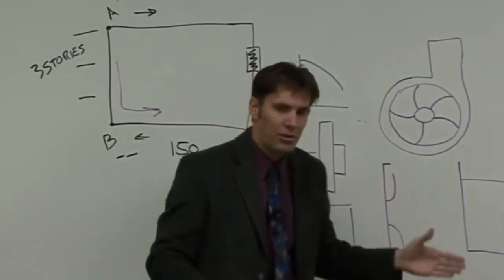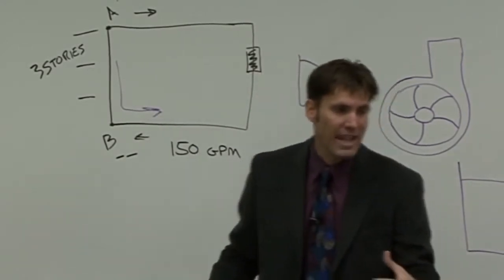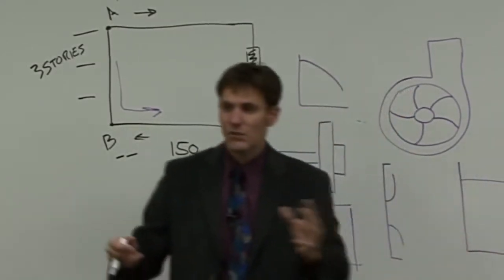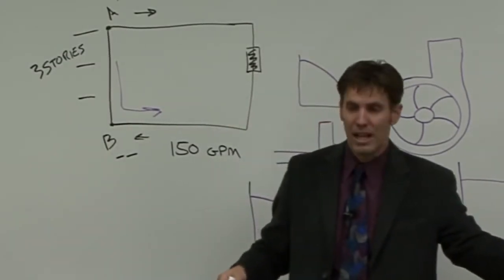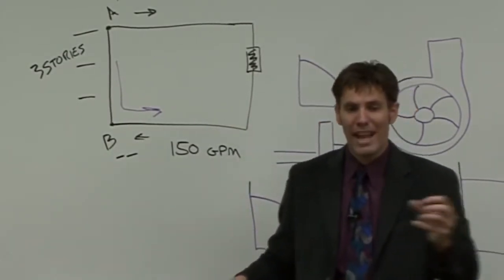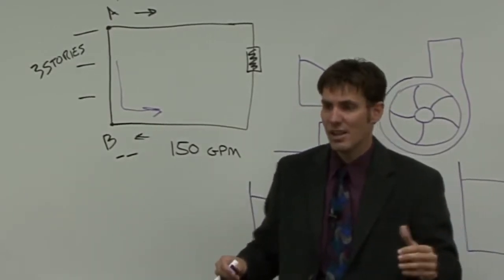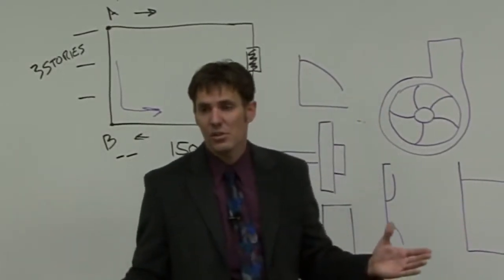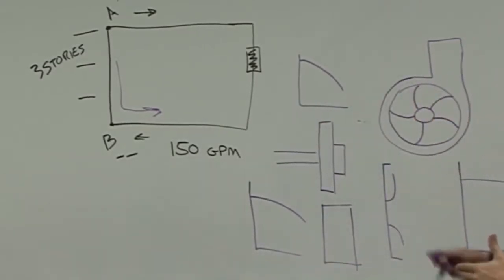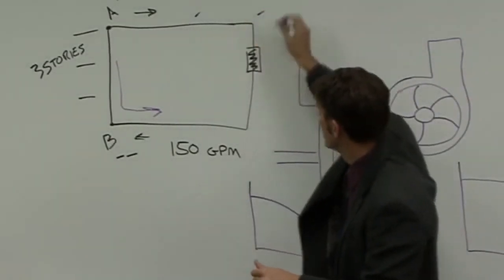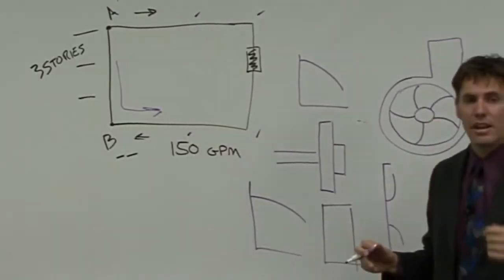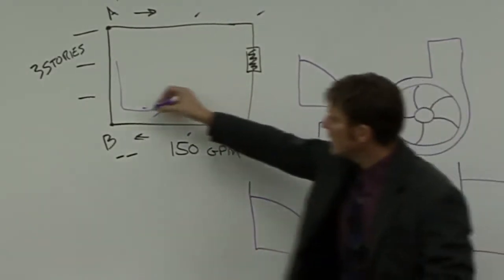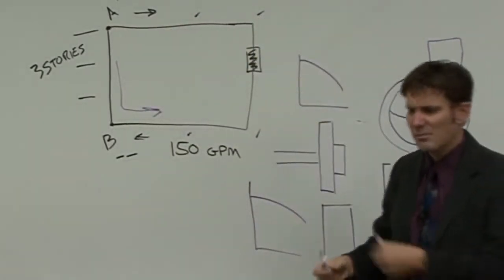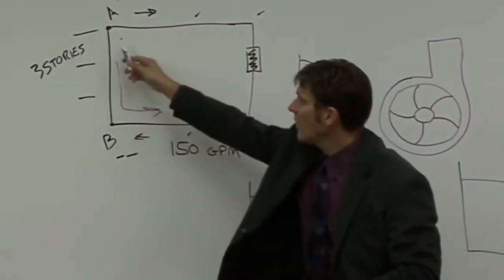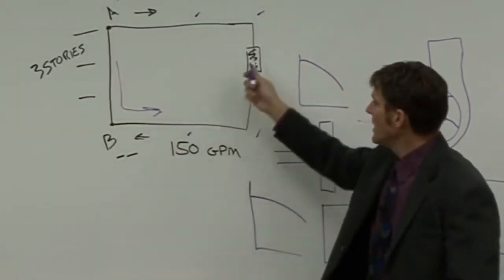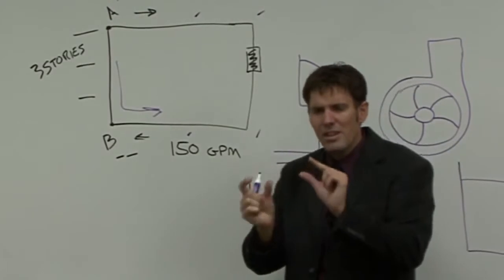This is why it can be very difficult to take a pump that's actually been manufactured for the agriculture business and use it in HVAC, because agriculture applications might not have the same flow and head conditions that we have in HVAC. I see engineers make a mistake when sizing their pumps or as they calculate the pressure through the system. It's usually pretty standard in a closed loop hydronic system, because we don't have to lift the elevation. It doesn't matter how tall the building is. Really, it matters how long our piping is and how many zones we have. So typically we're within a pretty good range.